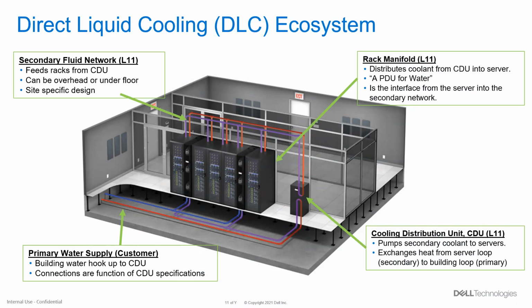Briefly, I wanted to make sure it was clear that when you operate a direct liquid cooled rack of servers, what you're really doing is setting up an ecosystem that enables these servers to run. What we have is an image here of racks of servers that are direct liquid cooled. The unit to the right is what's called a coolant distribution unit, and this is the main heat exchange element. The lines to the top show the purple water feeds that are the cool feeds to the IT. The red is actually the warm fluid exhaust that goes back to the heat exchanger from the racks of IT.